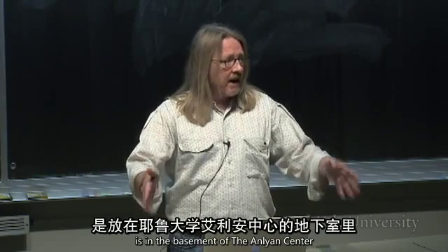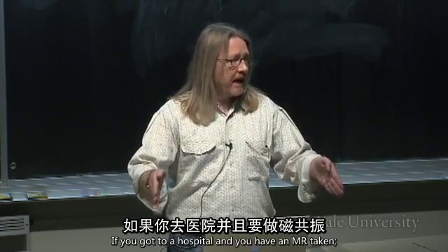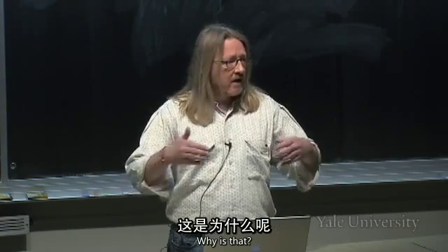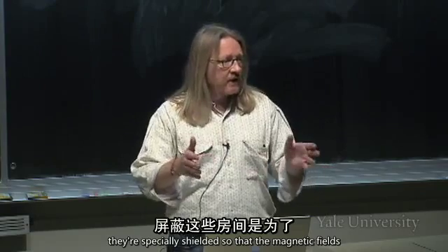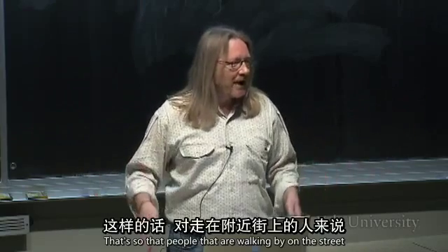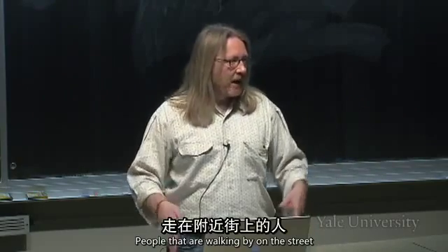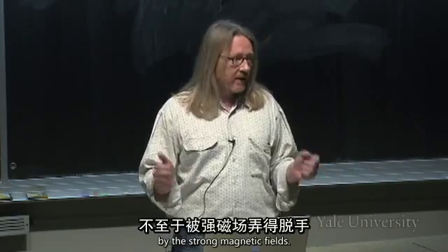Because of this, the MR facility that you will see here at Yale is in the basement of the Anlyan Center, and usually these machines are in the basements. If you go to a hospital and you have an MR taken, usually you go down to the basement. And why is that? Because they're put in rooms that are specially shielded, so that the magnetic fields cannot penetrate outside of the room. And that's so that people that are walking by on the street don't have their credit cards erased, right?